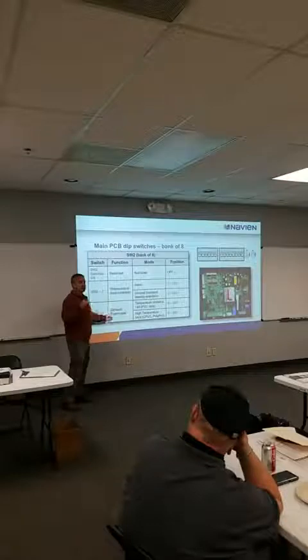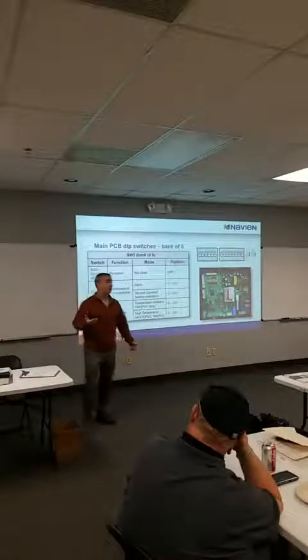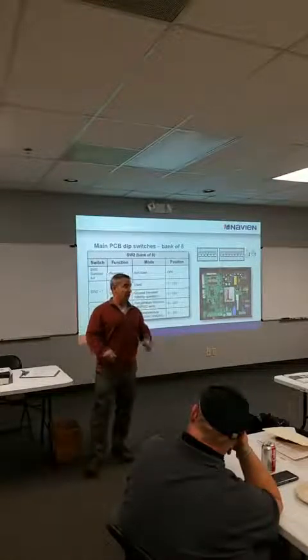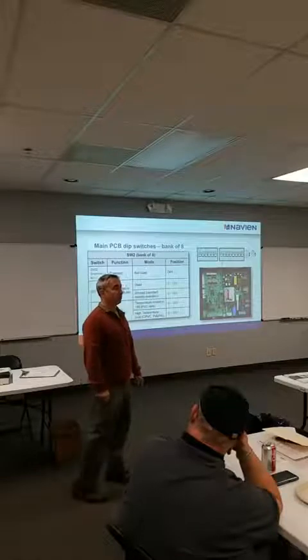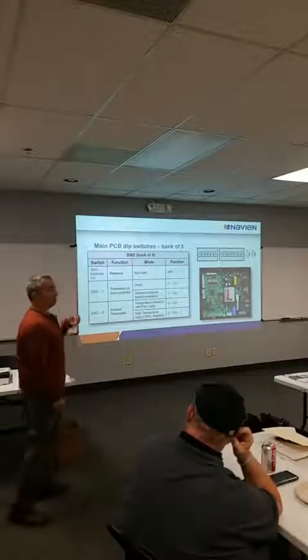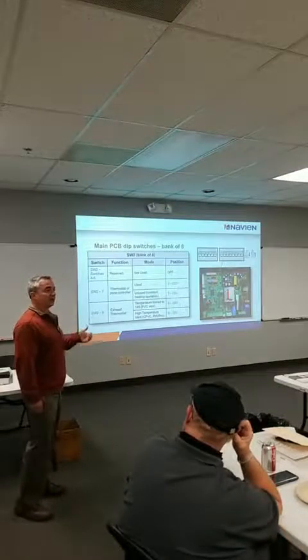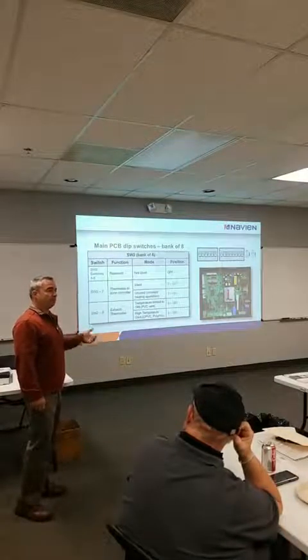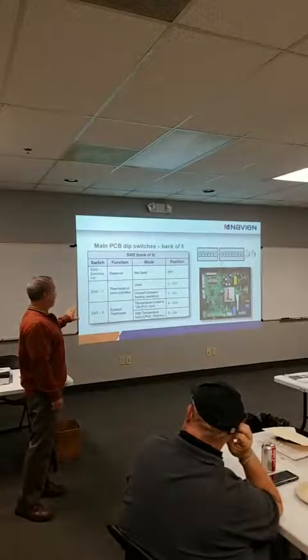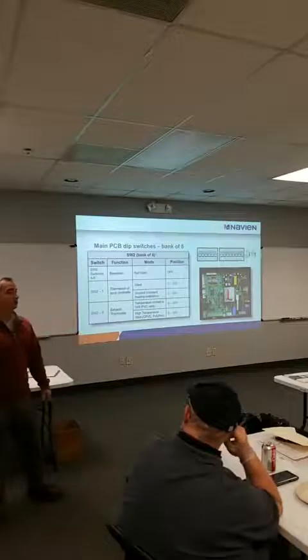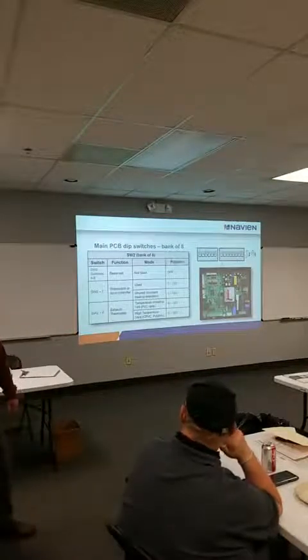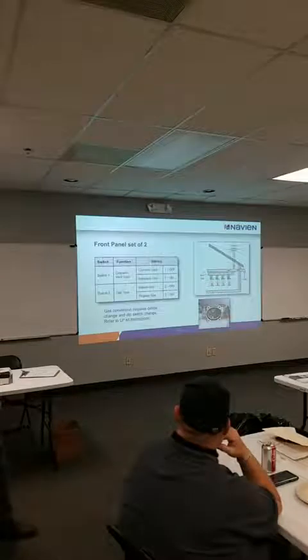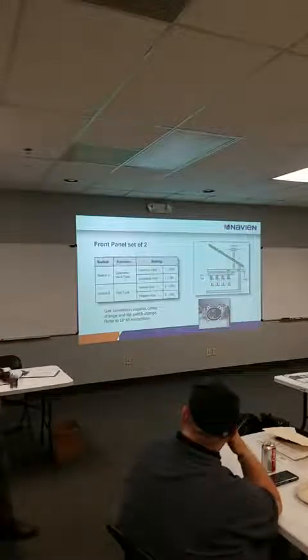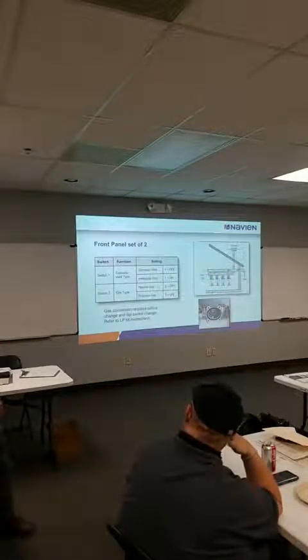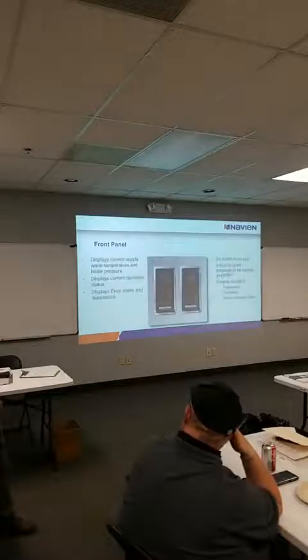And that's gonna keep that boiler at about 140 degree supply temperature, even if you crank it up to 180. And you're gonna see that on all of our equipment. We do that to protect the venting. So people that are doing the install have to manually change that and make sure they change their vent pipe. And then we just have some other gas type and then common vent or individual vent. That's an old picture, so I'm gonna skip by it.